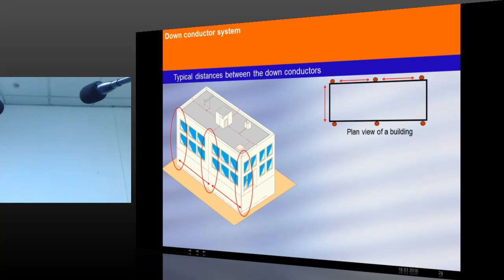In simple terms, for this particular building, if you have one down conductor, in the event of a lightning strike the whole current, this heavy current, maybe 100 kiloampere or 200 kiloampere, 10/350 microseconds, this much energy will flow through one conductor, and that current flow is enough to destroy your electrical and electronic equipment. Instead of one down conductor, if you have 6, then the current is divided into 6 parts. Current through each conductor is less, and magnetic effects are less.